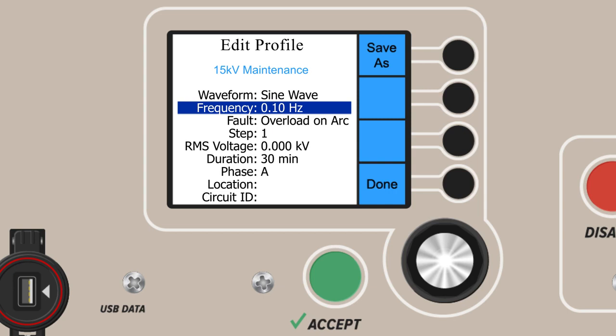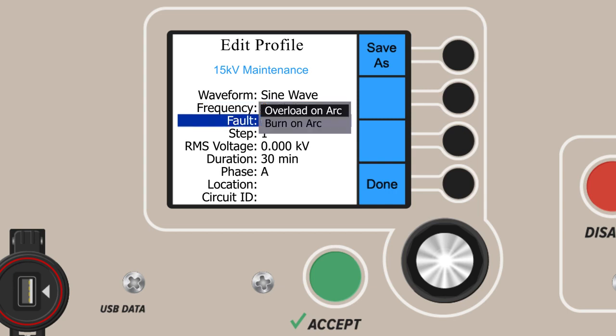After you've set the frequency, select your fault detection mode. With the Overload on Arc setting, when a fault is detected, the high voltage circuitry shuts down and the test is stopped. No more voltage or current are supplied to the device under test. With Burn on Arc mode, you can further burn and condition the fault for easier detection with other common cable fault location equipment. This should be used for troubleshooting purposes only. We will choose Overload on Arc, our default mode.